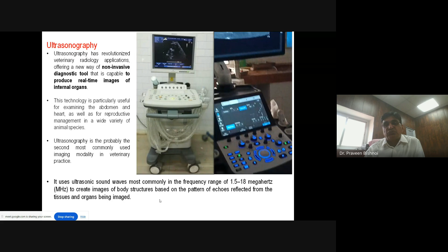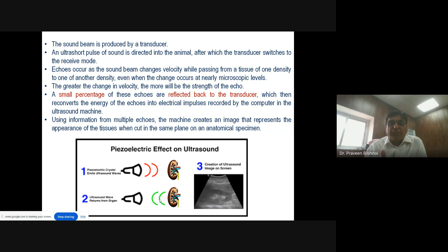Now, as far as the functioning of the ultrasound, a sound wave is produced by the transducer, and this ultra short pulse of sound is directed to the animal, after which the transducer switches to receiver mode. Once the transducer produces a sound wave, it goes into the body and strikes the internal organ. Some of the sound wave will pass, some will be absorbed, and some will be reflected back. Then the same transducer becomes a receiver and sends the signals to the computer, and on the basis of the pulse echo principle, the computer displays the image on the screen.